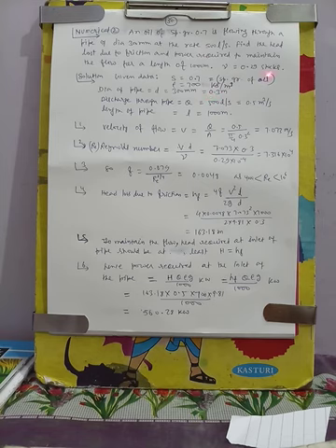Not everything will be given in the question, in the articles. By knowing the concept, we will have to estimate the meaning of this line, power required to maintain the flow. It means that at the inlet of the pipe, that much power should be available so that the flow will come out from the other side of the pipe. So head at the inlet should be at least the frictional loss in the pipe. So power required at the inlet is equal to HQ rho g by 1000, and H should be minimum the frictional loss, so H will be HF, which we have calculated here.